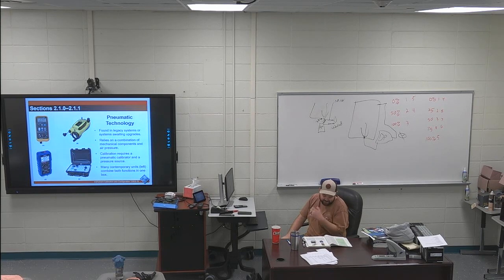My first highlight on 8 and 9 is on 213, Principles of Operation. The first sentence: a pneumatic differential pressure transmitter has a two-sided differential pressure capsule that receives two different levels of pressure and converts the difference between the pressures into a mechanical movement via a force bar. I underlined "converts the difference" and wrote out to the side "subtracts." So all it does is subtract the difference. You're taking your head pressure minus your zero and figuring out what your difference is.